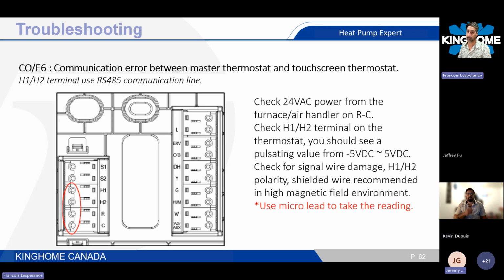I do have one more question. In the event that you're in a slab home or there's no basement, would you mount your mechanical room thermostat on the ductwork and then put the other thermostat on the wall, or how would you want that done? Yeah, you can do it like this. Basically, I use a junction box. The picture here is maybe not really accurate, but if you have a junction box, you can use those two holes right here and install that back plate on the junction box. It's much easier to do all the connections. Thank you. No worries. That white thermostat will not read the room temperature. The only one reading room temperature is the touchscreen thermostat at the moment.